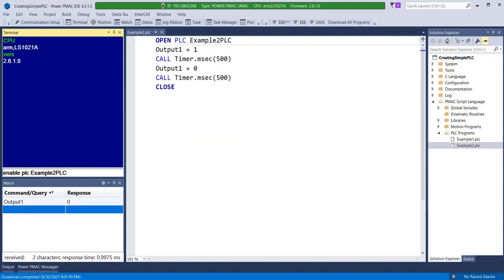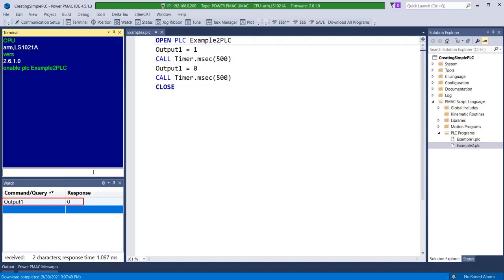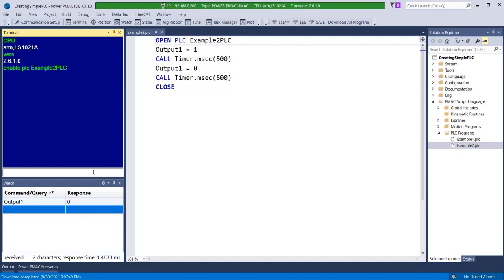This second PLC example already downloaded into PMAC demonstrates the use of a delay timer. Enabling this PLC toggles output 1 on and off every 500 milliseconds. Delay timers are essential to PLC programming for introducing discrete time delays to execute on-off logic but also to wait for certain status bits to take effect or events to occur circumventing the high speed computation of PLCs.